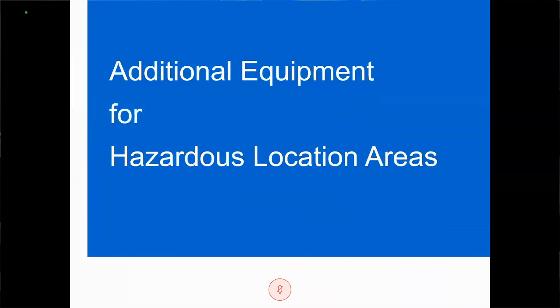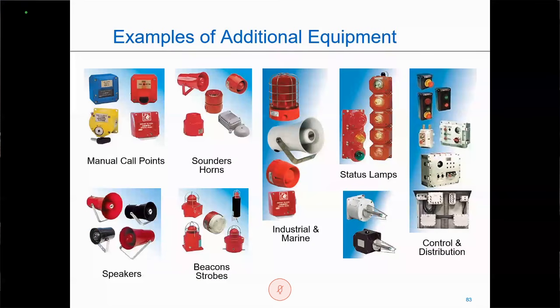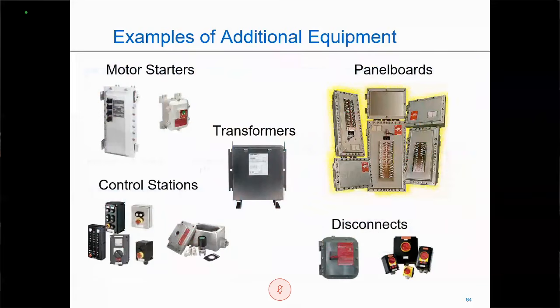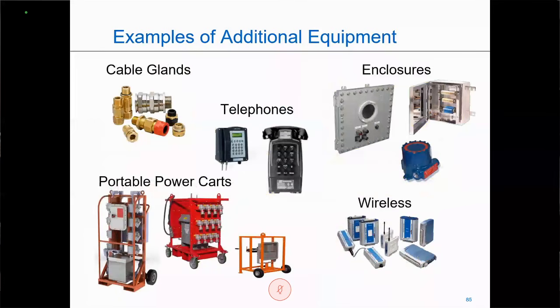Additional equipment that you might find in hazardous location areas: horns, strobes, speakers, motor starters, panel boards, disconnects, control stations. Cable glands. If we're having open cabling, we're going to find a lot of cable glands. If I have a Class 1 Division 1 unit, it's going to look something like this, or some type of configuration similar to this with all of the bolts. Class 1 Division 2, if it's housing an arcing source, may be some type of similar configuration, but if it's Class 1 Division 2, just a splice box or terminal housing, now I'm just worried about my environmental protection, and so I may just have a stainless steel or fiberglass unit.